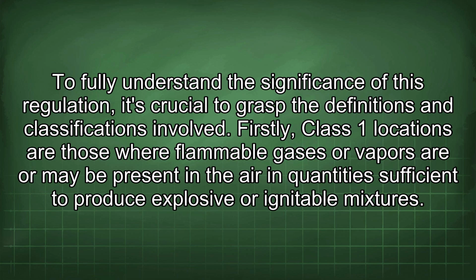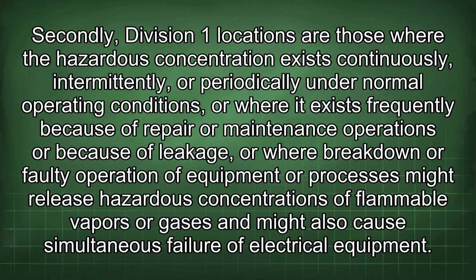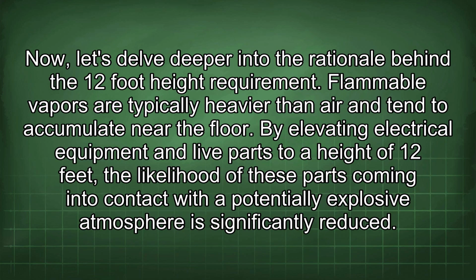Firstly, Class 1 locations are those where flammable gases or vapors are or may be present in the air in quantities sufficient to produce explosive or ignitable mixtures. Secondly, Division 1 locations are those where the hazardous concentration exists continuously, intermittently, or periodically under normal operating conditions, or where it exists frequently because of repair or maintenance operations or because of leakage, or where breakdown or faulty operation of equipment or processes might release hazardous concentrations of flammable vapors or gases and might also cause simultaneous failure of electrical equipment. Now let's delve deeper into the rationale behind the 12-foot height requirement.